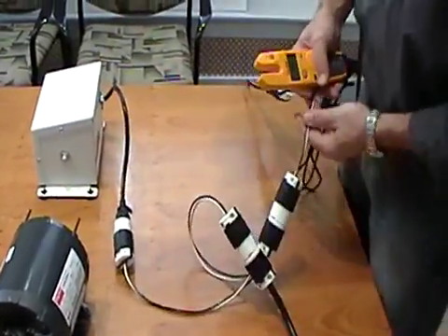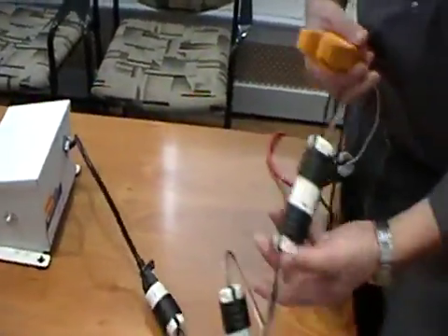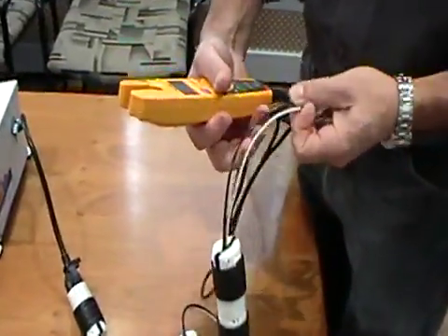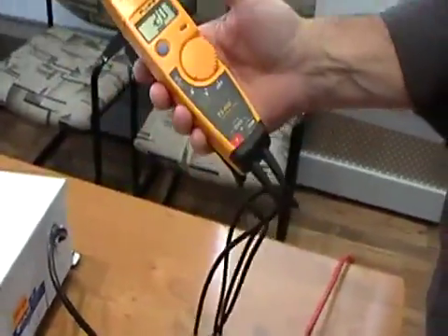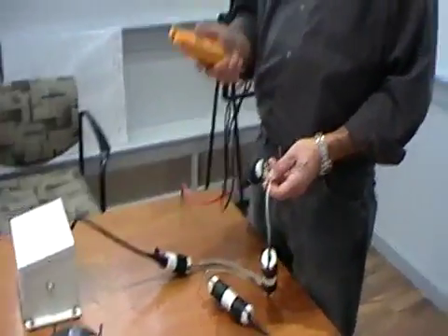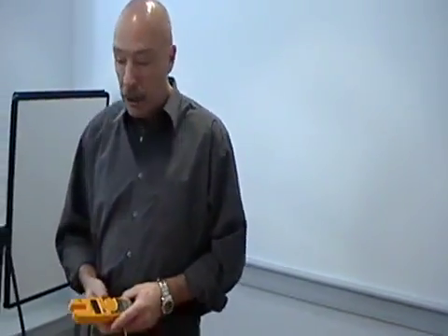Now we're going to check the power on the distribution system. In theory, we should have eliminated all that wasted current off the distribution system from this point back. We're at 2 amps. We've taken 60% of the wasted current off of the distribution system, trapped it at the motor load. So what this does is greatly reduce the strain on the distribution system. Probably 30% of the applications that we deal with are industrial facilities who think they need a new service entrance because their distribution system is maxed out. This is pretty good proof that we can eliminate that problem just by installing the capacitors.